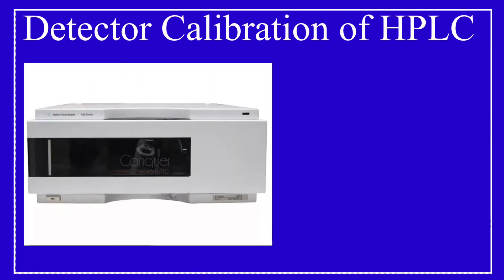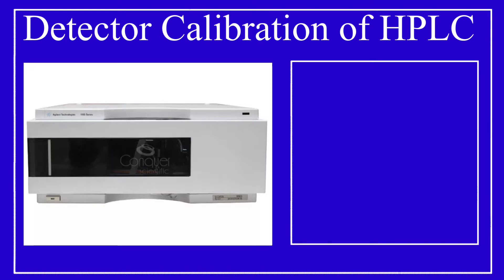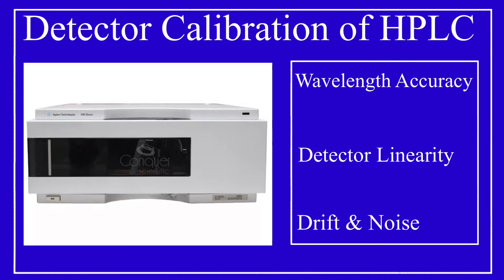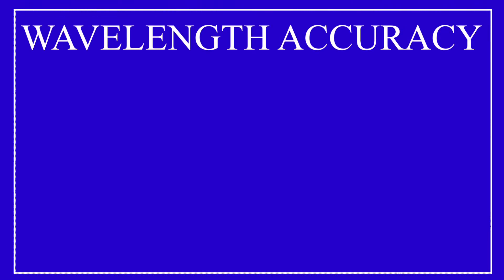The detector of HPLC is calibrated with the help of three calibration parameters, and those are: wavelength accuracy, detector linearity, and drift and noise. Let us learn about the wavelength accuracy test first.